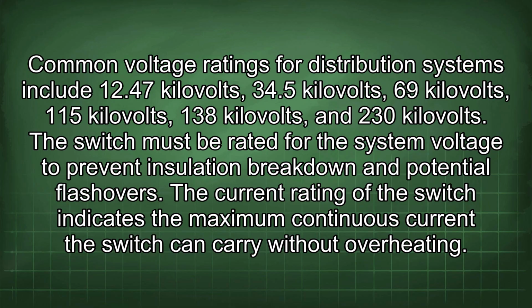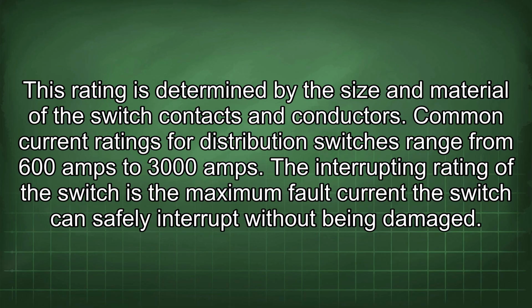The current rating of the switch indicates the maximum continuous current the switch can carry without overheating. This rating is determined by the size and material of the switch contacts and conductors. Common current ratings for distribution switches range from 600 amps to 3000 amps.